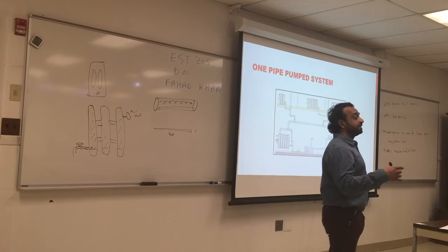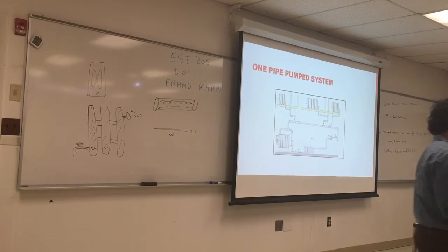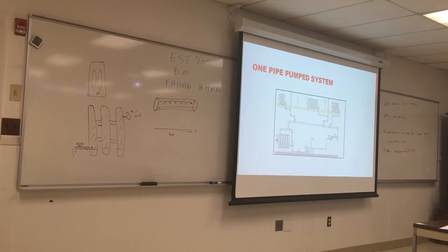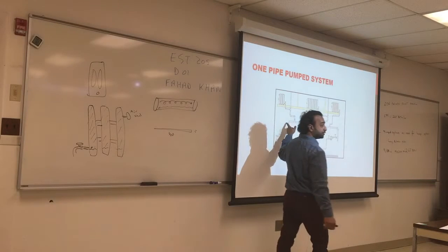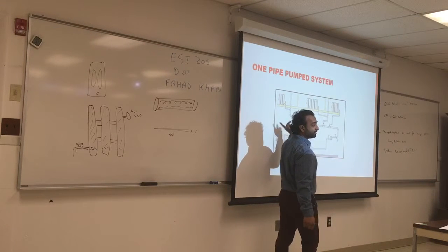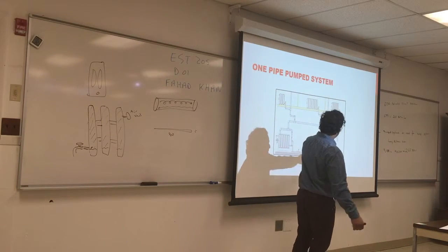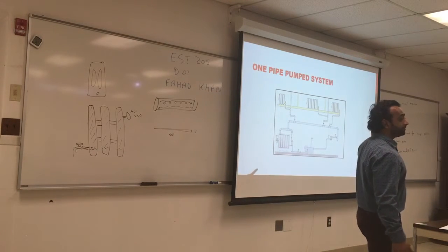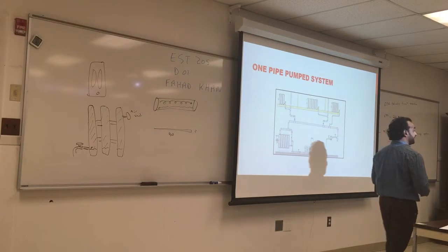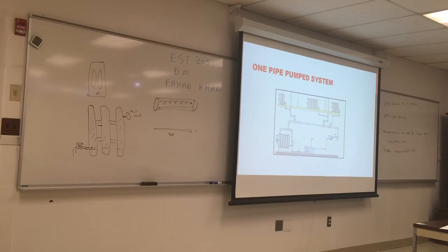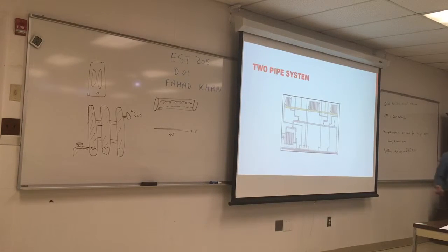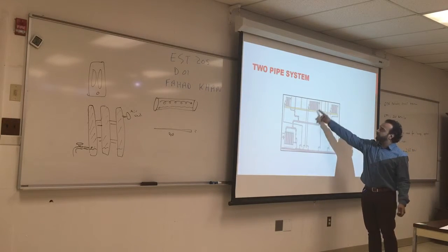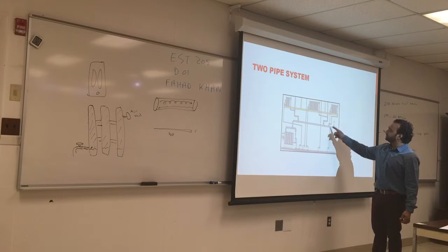If the system was designed for steam and you want to switch to hot water, of course you're going to have to pump that. You're going to install a pump coming out of here, and it will pump to the entire pipes. You have to put returns on that system too. For radiators that work with hot water and steam, it has to be a 2-pipe system. It can't be a 1-pipe system. A 2-pipe system again has pipes and returns coming to the same header.